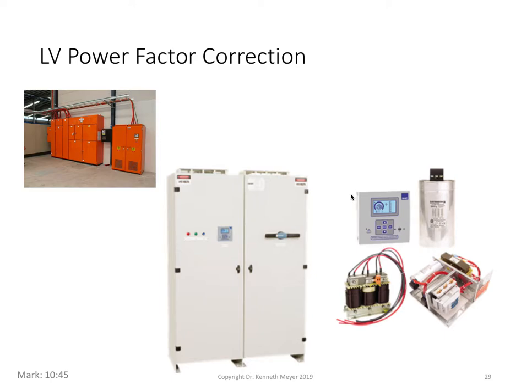And it switches in and out blocks of capacitors. And you can see here the capacitors. These are three-phase capacitors in this tin can arrangement. There's some fuses and or circuit breaker protection. And there's also a small amount of inductance added, not to offset the capacitors themselves, but just to stop inrush current, so that when you turn the things on, you don't suddenly pop the protection fuses, because when a capacitor is first turned on, it looks like a short circuit and can have a relatively high amount of inrush current. So they add a little bit of inductance in the front end just to slow the inrush current.